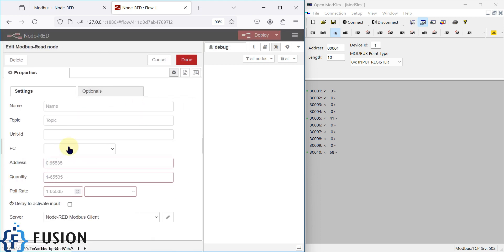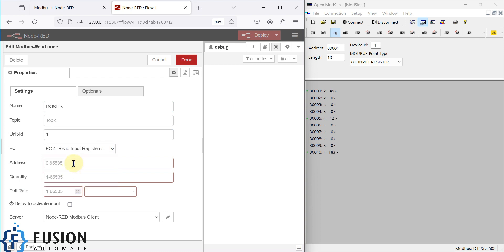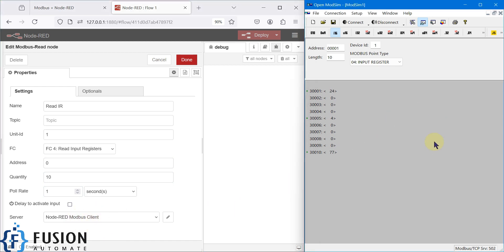We are going to read the input register. The unit ID is 1, and the function code we have to select is 'Read Input Register'. The starting address is 0, the quantity we want to read is 10, and the poll rate is 1 second.